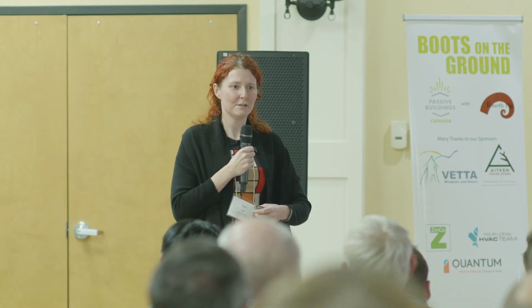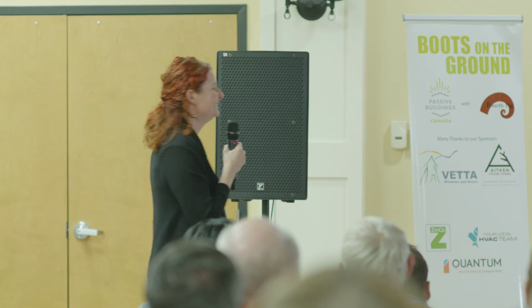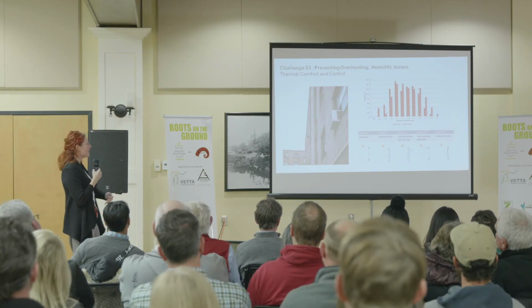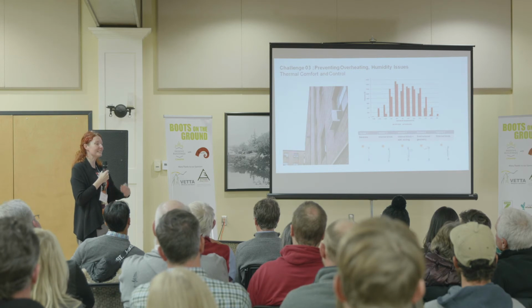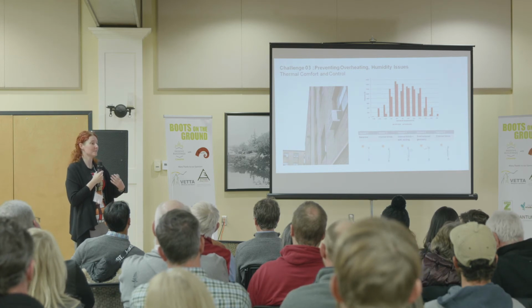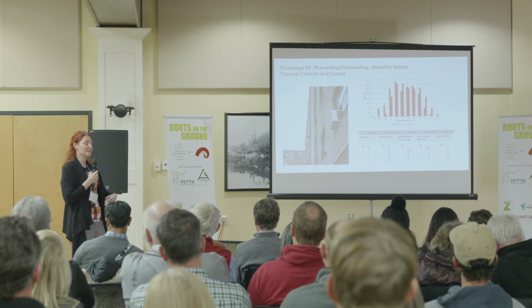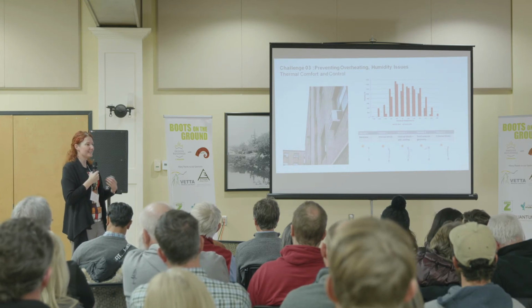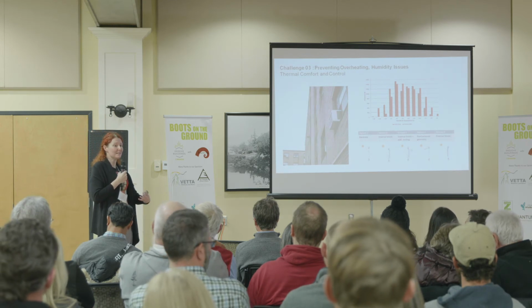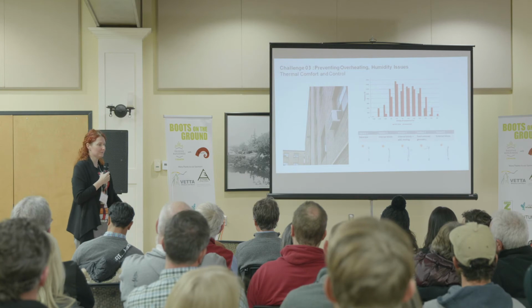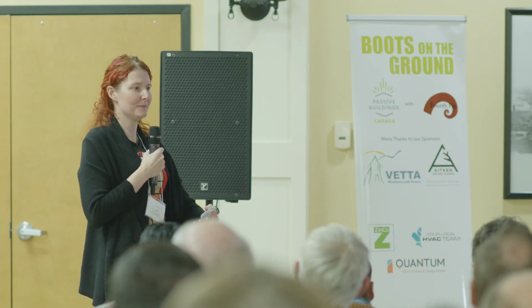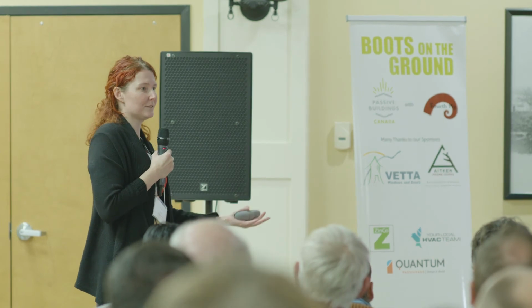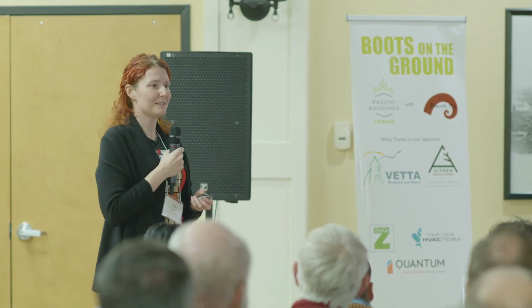Then I looked over at them and said, wait, did you look at humidity? And they said, why would we look at humidity? They came back about three hours later and said, we need cooling. What we learned is that Passive House is an amazing standard, and we need more pieces of equipment that can deal with dehumidification, because in Ontario, humidity is going to be a bigger challenge than active cooling. So we're adding active cooling to this building. We only need the dehumidification—we don't really need the temperature control—but we're going to get both, because there aren't a lot of good pieces of equipment that can do dehumidification without active cooling. So stay tuned, and if you know anyone developing good tech for this, let me know.